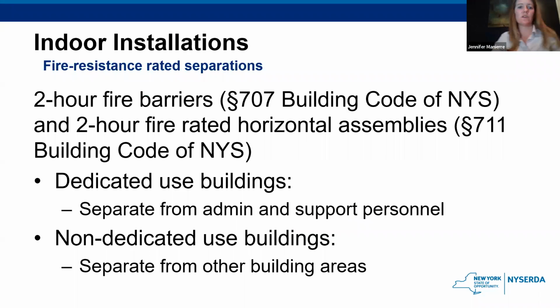Okay. All of them need 2-hour fire barriers, walls and ceilings. In dedicated use buildings, those barriers need to separate that potentially up to 10% admin area from the rest of the system. And in non-dedicated use buildings, the energy storage systems need these fire barriers around them to separate them from any other part of the building that's not the energy storage part.